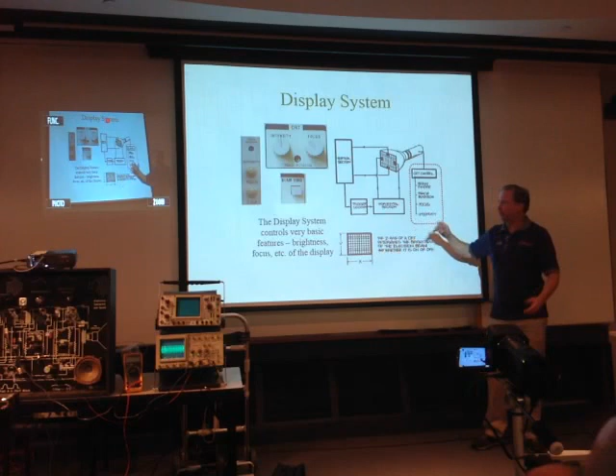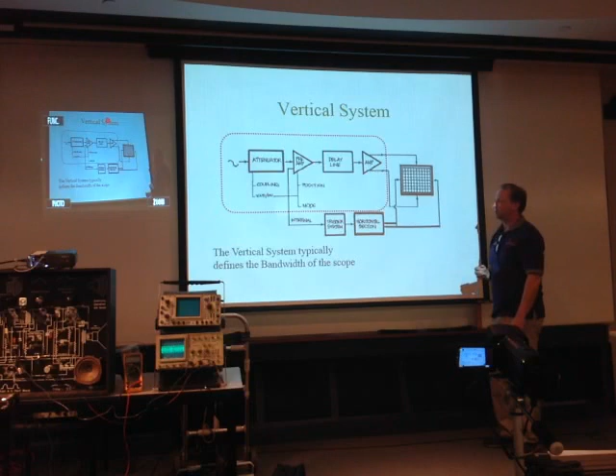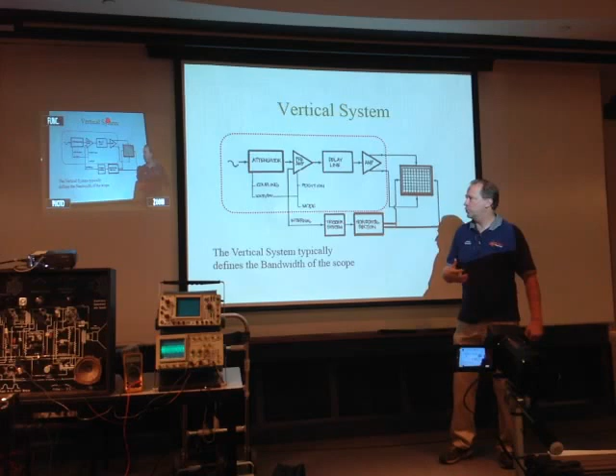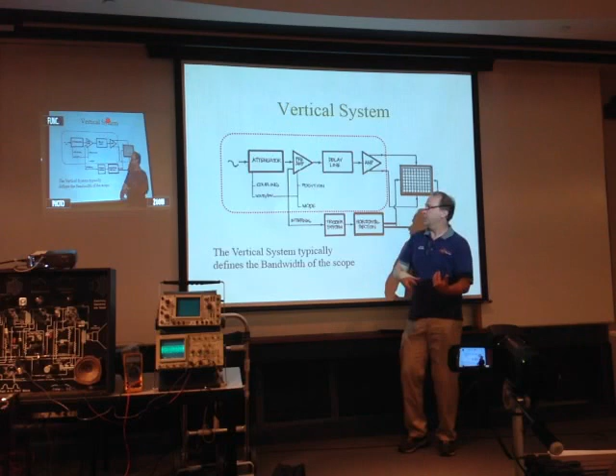The vertical system. This is one you're going to use probably the most. And what this does is control how many volts it takes to move 1 division or 2 divisions or 3 divisions on the screen. Okay? You've got an input signal coming in, and there's a number of controls that we use to process that signal as it comes through. Okay, amplify it, attenuate it, move it around, change its position, that type of thing.